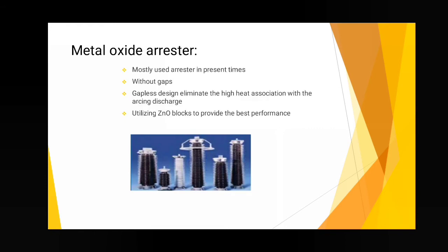Metal oxide arrestor. Nowadays, the widely used arrestor is metal oxide arrestor. Metal oxide arrestor has no gaps. The gapless design of metal oxide arrestor eliminates high heat associated with the arcing discharge. Metal oxide arrestor utilizes zinc oxide blocks to provide the best performance. The below diagram is metal oxide arrestor.